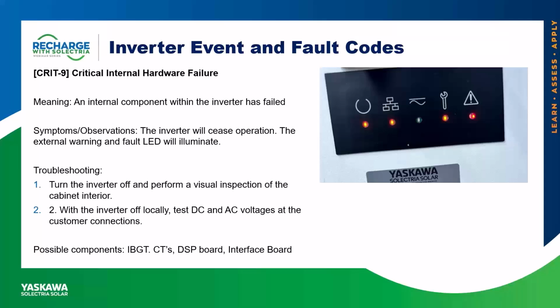This code can indicate different issues depending on the adjacent hex value it displays in the event and fault log. The code itself is more direct than others we've previously discussed, in contrast to where other codes may be byproducts of the situation. For example, if Crit 9 occurs, you may also see some corresponding warning codes that we have previously mentioned. The hex value recorded can allude to the particular component that may have failed, but given the nature of the code, it could be one or more.